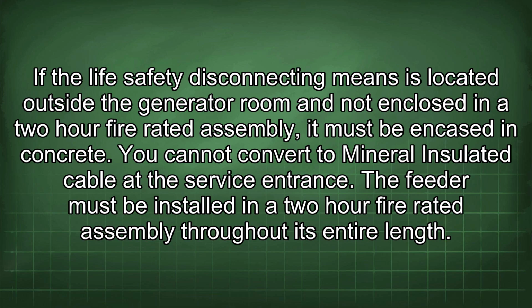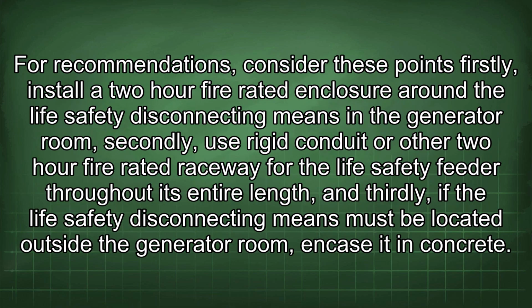You cannot convert to mineral insulated cable at the service entrance. The feeder must be installed in a 2-hour fire-rated assembly throughout its entire length. For recommendations, consider these points. Firstly, install a 2-hour fire-rated enclosure around the life safety disconnecting means in the generator room. Secondly, use rigid conduit or other 2-hour fire-rated raceway for the life safety feeder throughout its entire length. And thirdly, if the life safety disconnecting means must be located outside the generator room, encase it in concrete.